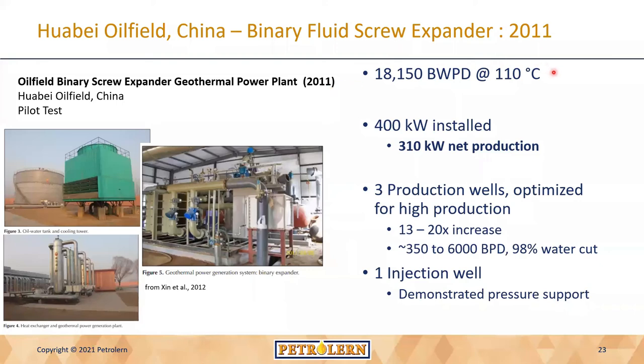This resource was about 18,000 barrels of water per day at 110 degrees Celsius, or about 230 degrees Fahrenheit. They ultimately installed 400 kilowatts, was the size of this screw expander. They had a gross production of 360 kilowatts and a net production of 310 kilowatts.